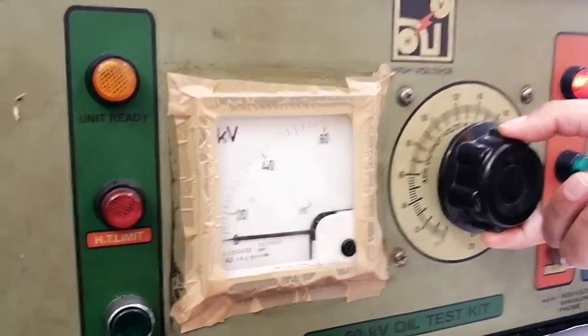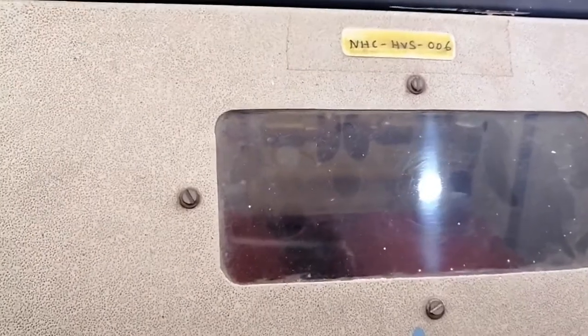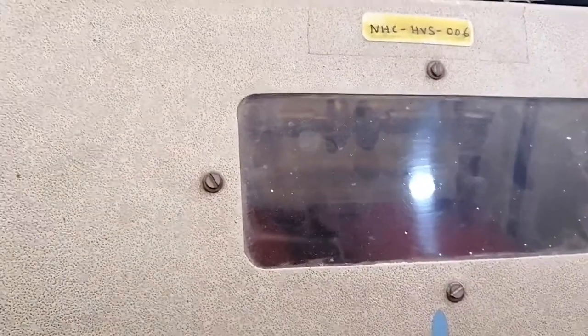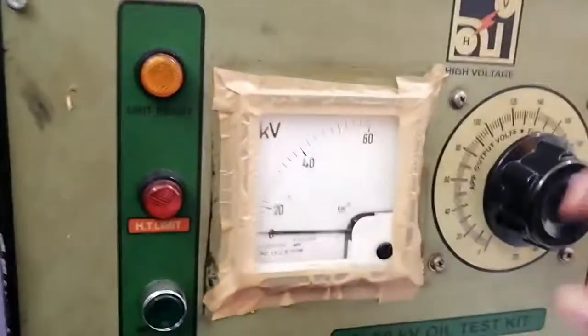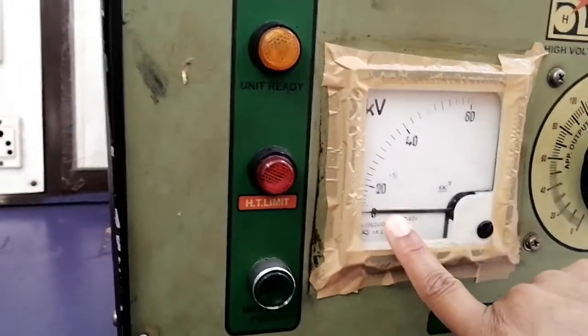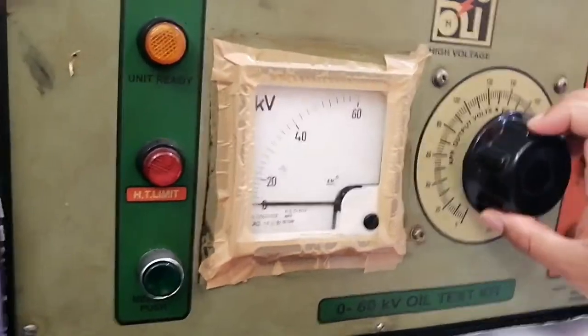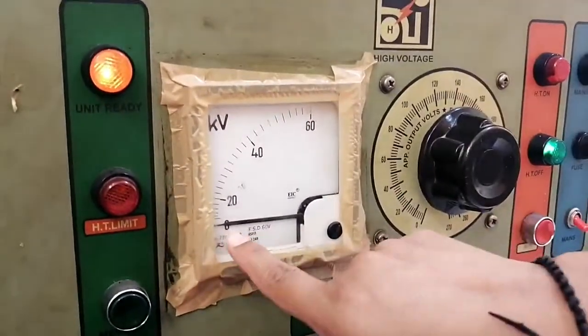As you apply the voltage, you can see the spark in the sphere gap through the window provided. Keep observing. Once the breakdown strength of the oil is reached at the kilovolt value applied, you can see the spark in the sphere gap. This is the spark you have seen. But the voltmeter has already gone to 0 when I started applying this voltage, and I could not notice the voltage value.